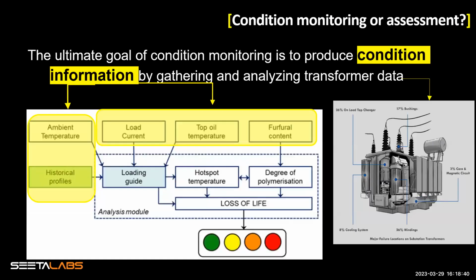The point at the end of the story is that your ultimate goal should be producing condition information. With the help of moisture measurement, you can tell the extent of degradation of insulation paper, whether mechanical, thermal, and dielectric strength has reduced, and whether sludge formation is happening because of excessive paper charring. You can tell a lot. When you can identify the failure fault or failure mode in action, you can take preventive actions, solve problems, and save money, which is what industries are all about.